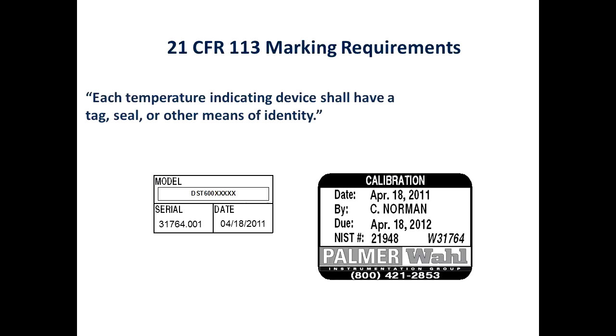21 CFR, the marking requirements, it does state each temperature indicating device shall have a tag, seal, or other means of identity. At the factory here, we put the model number, serial number, the date of manufacture on it. And then this is a sample of our calibration sticker. We use a Brother P-Touch label maker. They're relatively inexpensive labels. They come with software, and you can create just about any label you want. You're limited to the colors of materials, but we use a silver with black, and they're a very durable label. And then you can see we've got the date it was calibrated. Now this is an old one, obviously.